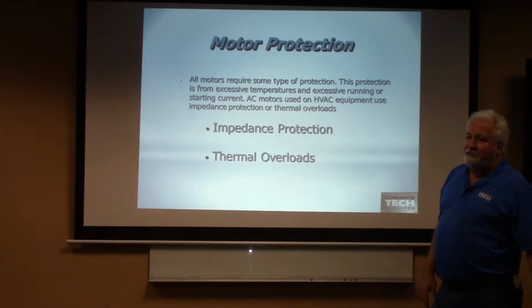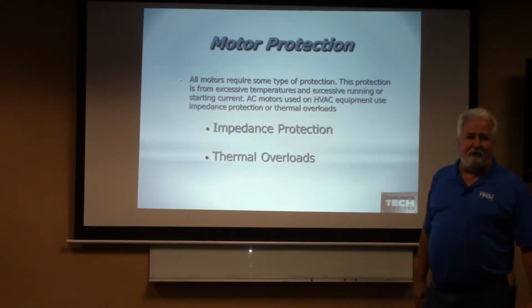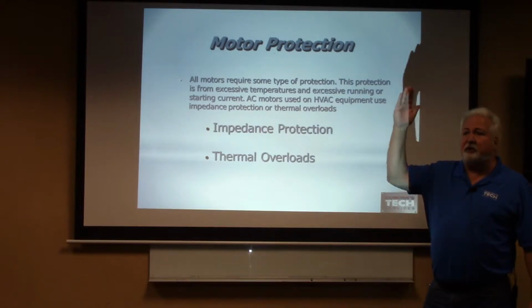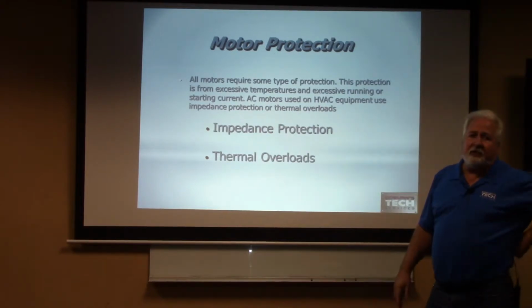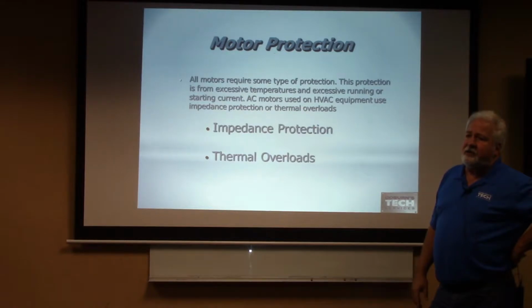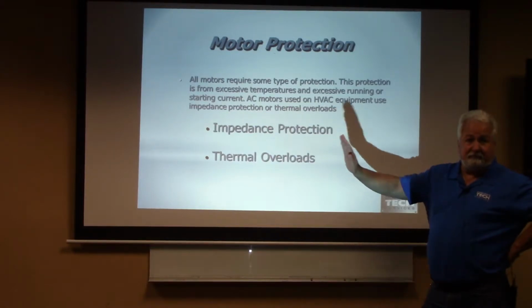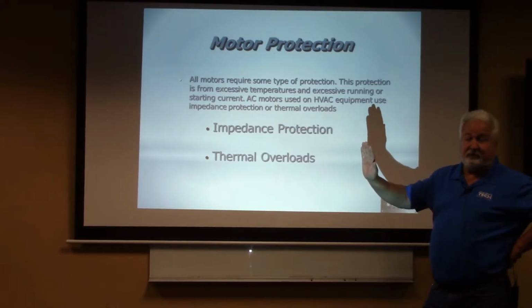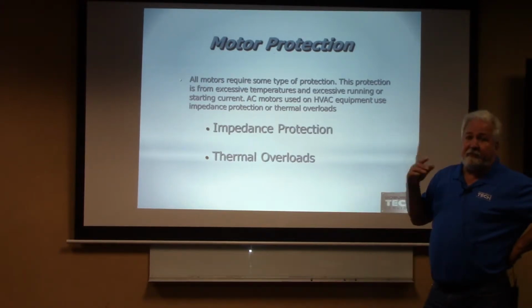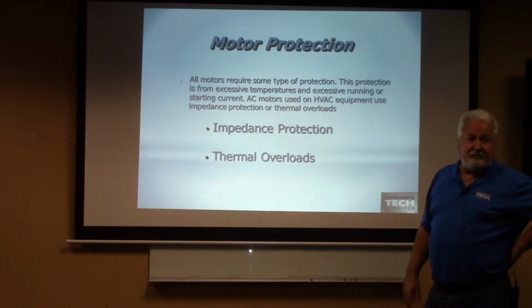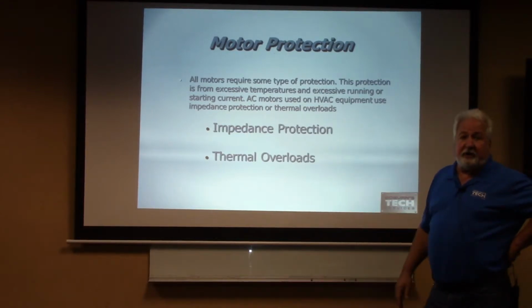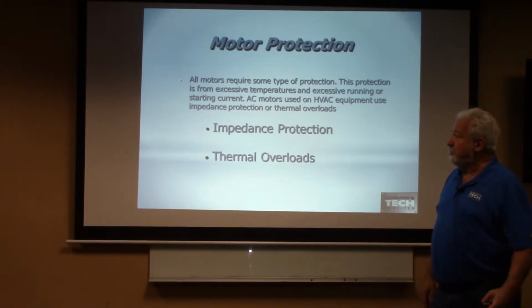Motor protection. There are 2 types of motor protection. Typically what you're going to see is a thermal overload. It's going to be that switch that opens up and shuts off. There is something called impedance protection, and that's typically going to be on your shaded pole motors. The impedance protection means it's going to impede the voltage. That means it's going to be what? Slowing down the voltage. Yes, resistance. So when it does that, if I can slow that voltage down or stop the voltage, what's going to happen to that motor? There it is. So typically on your shaded pole motors you can have impedance protection, and on all your other motors you're going to see out there, you typically have thermal overloads.